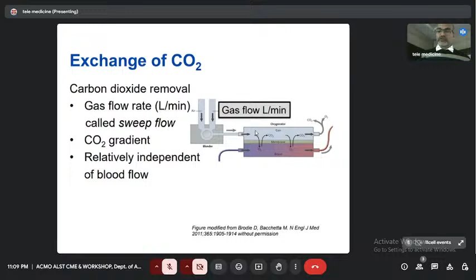When the flow we are talking about is in the range of 3 to 7 liters, we need really high bore, quite thick cannulas. According to the traditional Poiseuille's formula, the cannula should be large bore and short, but because of the risk that they might accidentally come out, which would be very catastrophic to the patient, they are not very short.